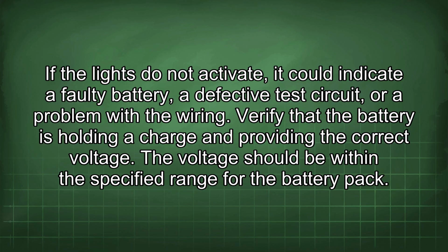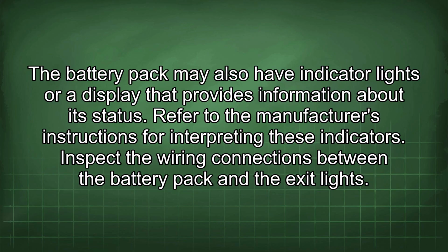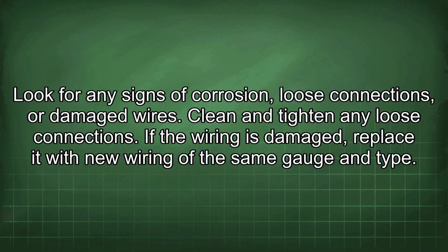The voltage should be within the specified range for the battery pack. The battery pack may also have indicator lights or a display that provides information about its status. Refer to the manufacturer's instructions for interpreting these indicators. Inspect the wiring connections between the battery pack and the exit lights. Look for any signs of corrosion, loose connections, or damaged wires. Clean and tighten any loose connections. If the wiring is damaged, replace it with new wiring of the same gauge and type.